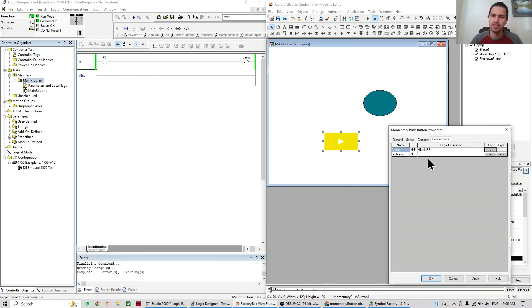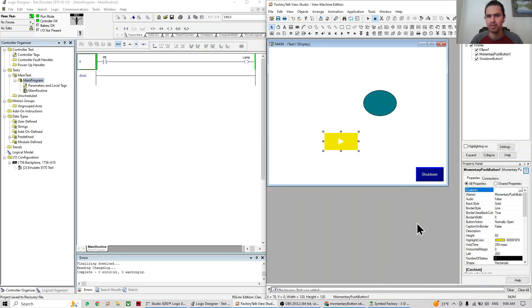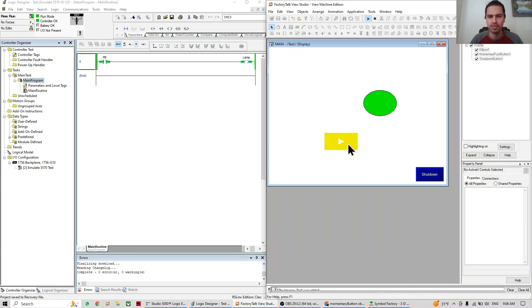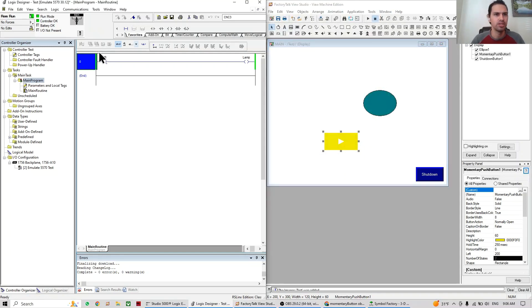There are two different things here. First is the Value — what the HMI or FactoryTalk View sends into the PLC. The other is the Indicator. If you don't put anything in the Indicator, it will change along with the Value — which is what's happening right now. Whenever you change the value, the indicator changes. But you can assign a different tag to the indicator.